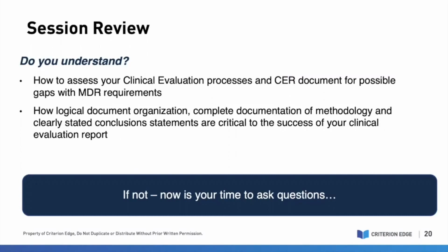What you can't do is use your own data on your own device to establish your own safety and performance state-of-the-art criteria. You can't do that. What we have done is use competitor devices data and pooled meta-analyses and systematic literature review of pooled data sets in which your device may be present, but is also present with all of its other competitors. So I hope that helped to answer the question.